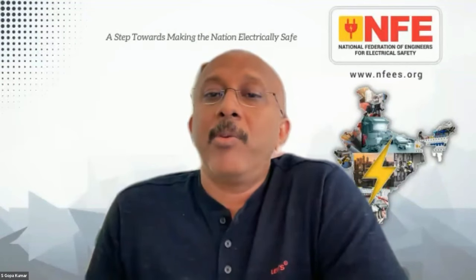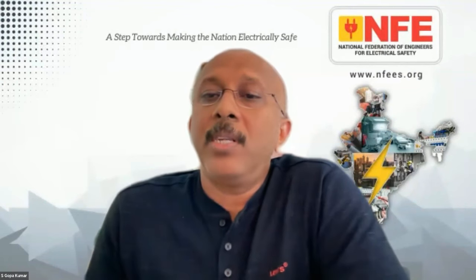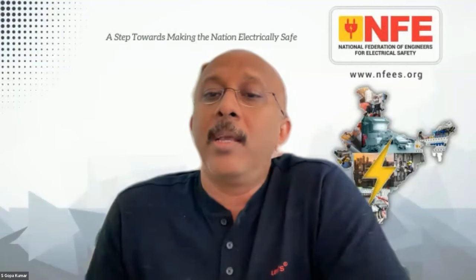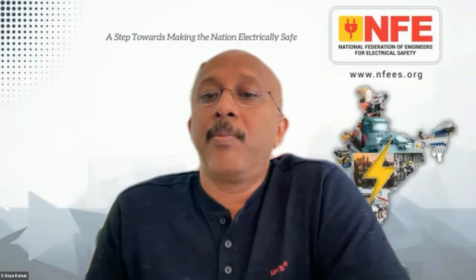So there is a question from Mr. Amrit Lal. For the public network of residential and small commercial installations, is the supply by TNS or TNC in the UK, for a new network? Well, TNC generally is frowned upon. TNC actually refers to the supply distribution anyway. When you have TNCS, it's separate within the installation. TNC is not permitted within a fixed installation, but the regs also say you can use it if you meet a whole load of other criteria. Because it's deemed quite dangerous within an installation, it's always worth separating the neutral and earth.